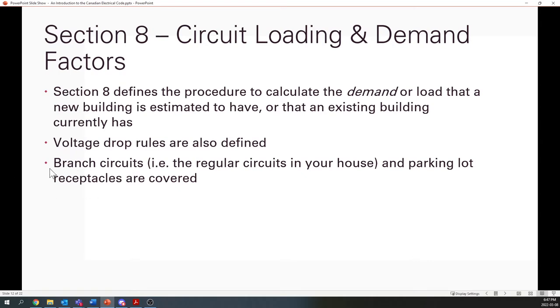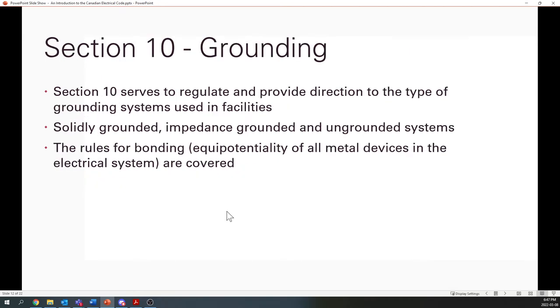And then section 8 also covers the rules for branch circuits, how many receptacles can be on a branch circuit, that sort of thing, and the parking lot receptacles are also covered. So what's the demand that you can expect for receptacles in parking lots, how many receptacles should be per breaker, what's the load that you're going to expect, like I was just saying. So those are all things that are covered in section 8. Section 8 is used a lot of the time where you're designing a new building. You're going to be referring to it a lot to come up with those estimated loads that you might be looking for. And pre-existing buildings that have new construction is the same thing.